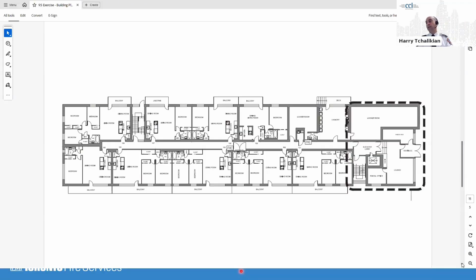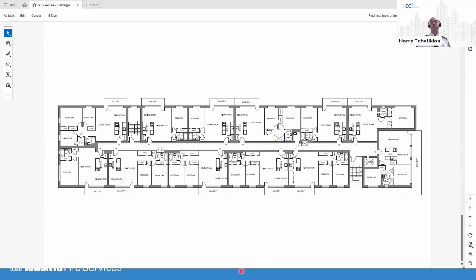So we have the ground floor covered. Now, because of this new requirement, let's look at the above floors. What you see here is floors 2 to 5, your standard floor plan. Presumably, if these are fed by a forced air fuel burning appliance, meaning there's ducting that the air was heated by a furnace, a fuel fired appliance, and that ducting originated from a fuel fired appliance service room and goes to each one of these suites, then all these suites now need a carbon monoxide alarm. Same thing with the corridor. If this corridor is served by forced air heating, then this corridor needs one for every 25 meters, and a corridor this length would need approximately one for every 25 meters. So about two carbon monoxide alarms would cover this corridor.